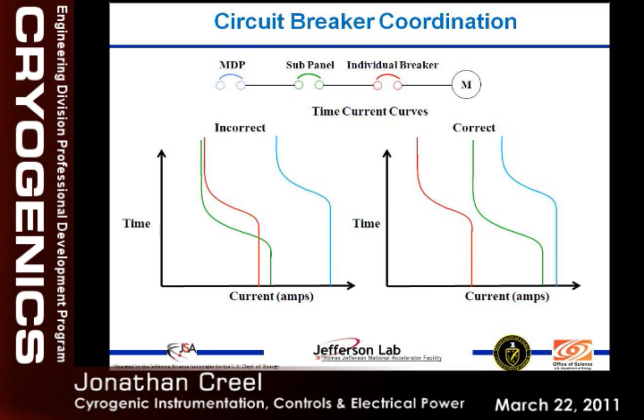And that's happened around here many times over the years. So when you're looking at installing equipment, this is one of the things that you should pay a lot of attention to. The object is to set this breaker as low as you can to make this function properly. So again, I don't have any formulas in my talk. It's mainly this type of bread and butter stuff that people tend to take for granted.